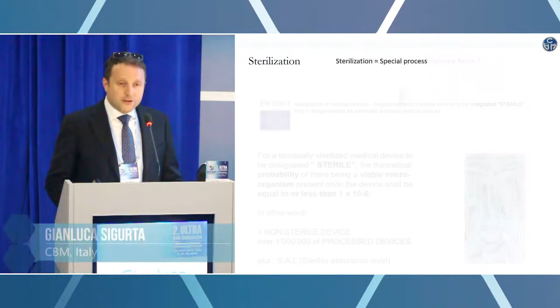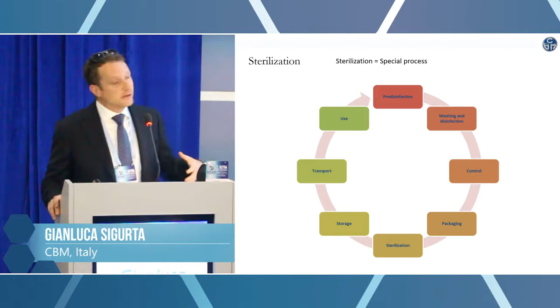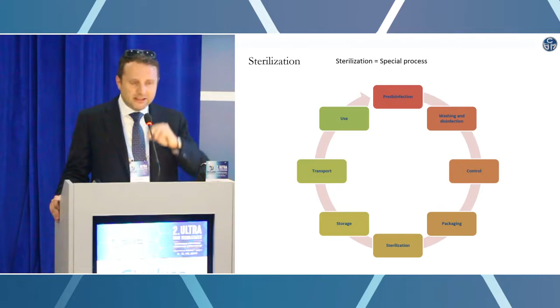So, for this reason, steam sterilization is considered a very special process. You may know the Deming circle. The steam sterilization process, or generally speaking the reconditioning process of a medical device, is not a line process but a circle process. And it's called special because you cannot know at the end of the process if you did a good job or not.